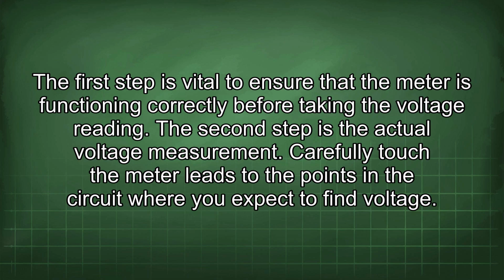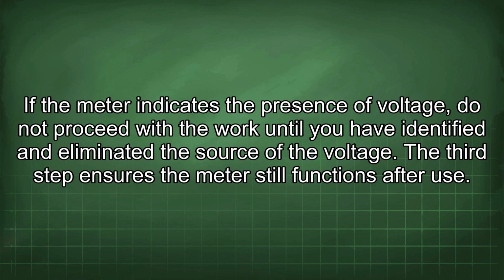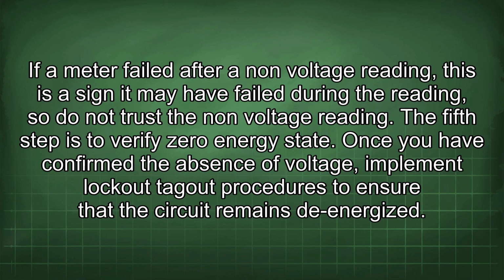The first step is vital to ensure that the meter is functioning correctly before taking the voltage reading. The second step is the actual voltage measurement. Carefully touch the meter leads to the points in the circuit where you expect to find voltage. If the meter indicates the presence of voltage, do not proceed with the work until you have identified and eliminated the source of the voltage. The third step ensures the meter still functions after use. If a meter failed after a non-voltage reading, this is a sign it may have failed during the reading, so do not trust the non-voltage reading.